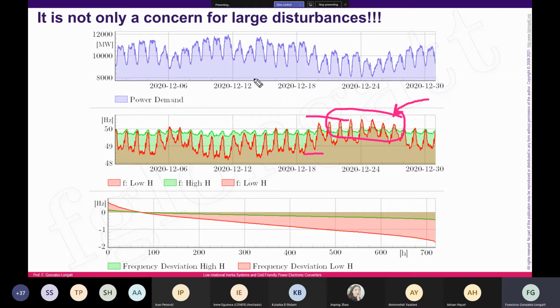The relationship between the maximum and minimum frequency values starts to become very large during the day, and you can see the frequency spending more and more time outside the regulation band. Many people are currently concerned about nadir and ROCOF, but in the future we also need to consider that the power system, during normal operating conditions in low inertia scenarios, can create instability problems.